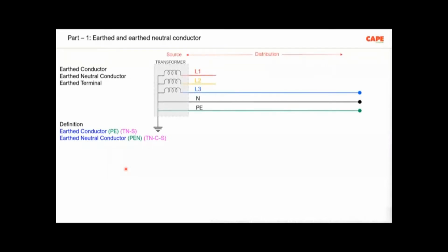But once you connect this electrical apparatus to your power supply, not only the apparatus has certain limitations. For example, line to neutral overcurrent and short circuit, the device is able to withstand by its own because it has an internal protective device and it will disconnect. Whereas in case of an earth fault, how you are connecting the earth outside is the important subject. Whether this protective device which is put inside the equipment is able to protect from an earth fault. So there, the system earthing comes into the picture, and system earthing is decided majorly by the power supply company, and the power supply company is supposed to follow the Central Electricity Authority regulations. This part I covered in my first part, 2 weeks back, but still I show you just for people who are new in this program.